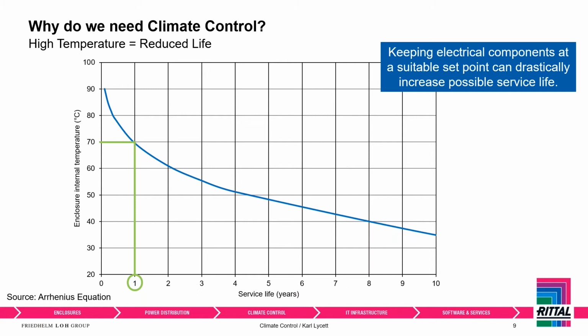If we're a bit more sensible, and as we mentioned, we take it back to that 35 degrees that we like to try and maintain as per the standards, we could see a tenfold increase in the life of our equipment. And that just makes a lot of sense because, if you're a maintenance guy listening to this, it's less work for you. You can be working on bigger things that are more important rather than having to fix random breakdowns on a line. So it's using your head and improving things in the right manner.